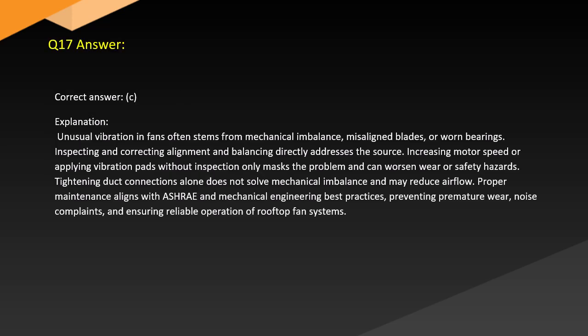Answer. Correct answer, C. Explanation. Unusual vibration in fans often stems from mechanical imbalance, misaligned blades, or worn bearings. Inspecting and correcting alignment and balancing directly addresses the source. Increasing motor speed or applying vibration pads without inspection only masks the problem and can worsen wear or safety hazards. Tightening duct connections alone does not solve mechanical imbalance and may reduce airflow. Proper maintenance aligns with ASHRAE and mechanical engineering best practices, preventing premature wear, noise complaints, and ensuring reliable operation of rooftop fan systems.